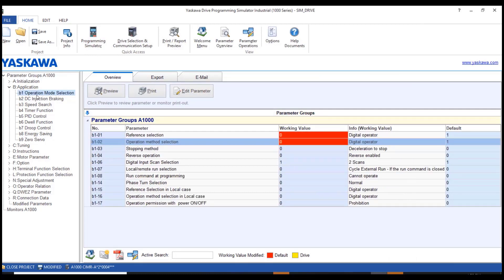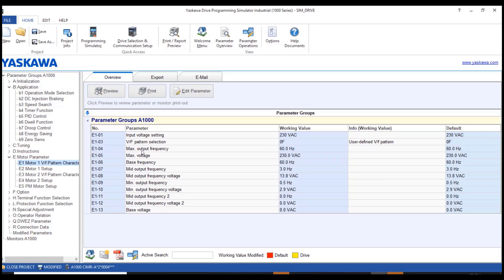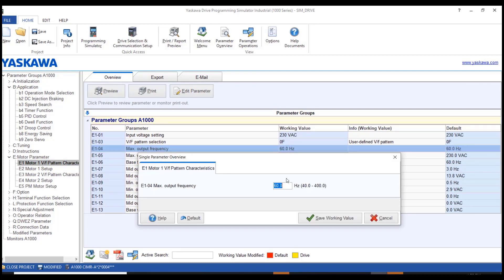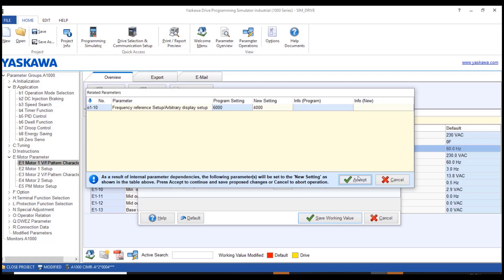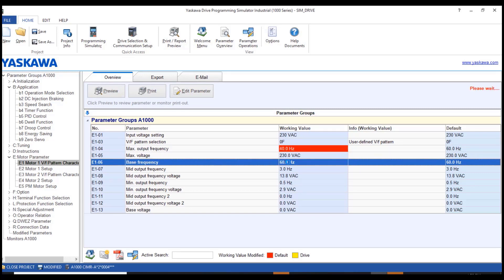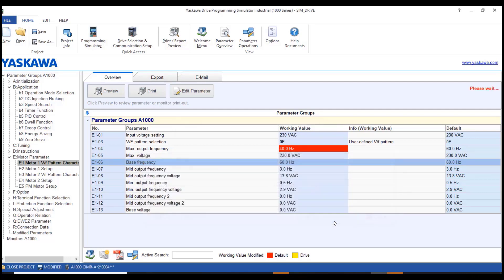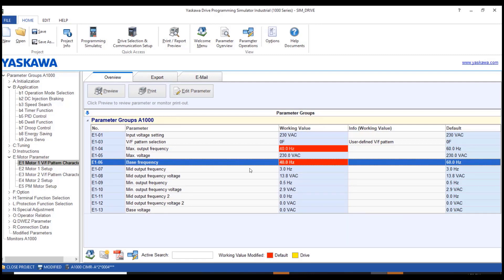If you want to change the maximum frequency, go to group E — motor parameters. Go to E1, where you will find the maximum output frequency, which is 60 Hz by default. You can change it to another value — I'll change it to 40. Click 'Save Working Value' and accept. Also change the base frequency to 40 instead of the default 60. Click 'Save Working Value'.